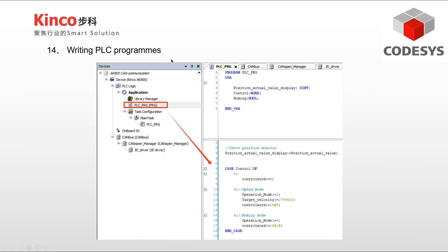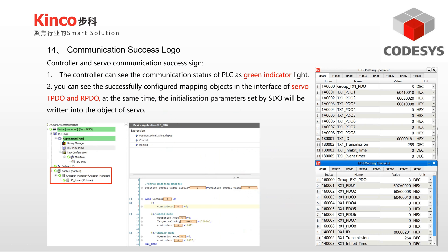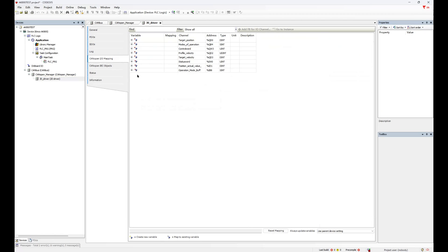Now you can start writing the PLC programs. When communicating with the PLC, the CAN bus communication indicator of Codesys will turn green. After starting the PLC, the preset PDO will be written to the servo. You can see on the servo whether the PDO has been successfully written. The preset SDO initial parameters will also be written to the corresponding object. In the CANOPEN I/O mapping, you can add the mapping of servo objects, and the mapped variables can be used in the PLC program.